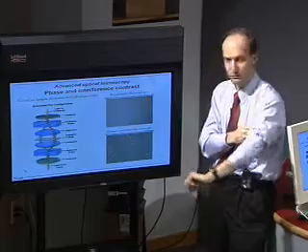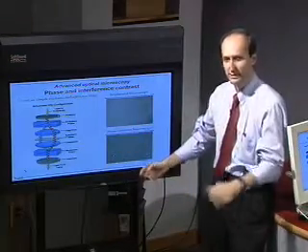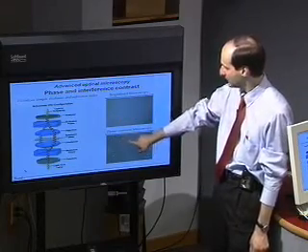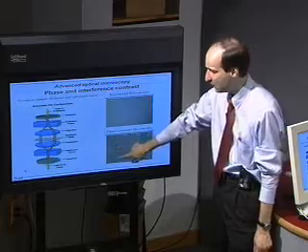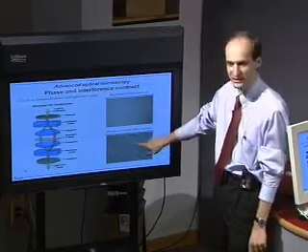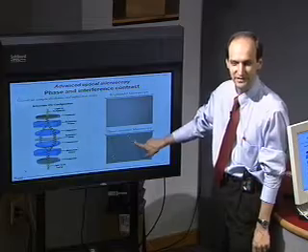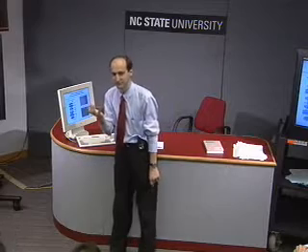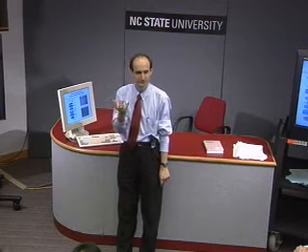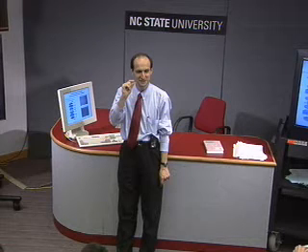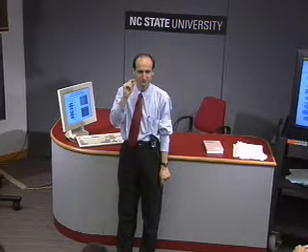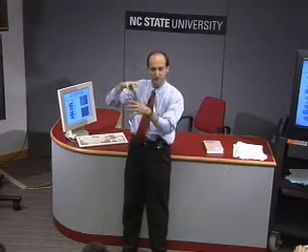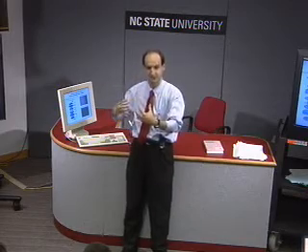This is realized in the microscope in a way about which you don't even care, but it allows you to immediately, instead of seeing this uniformly bright field, if you do phase contrast microscopy, you immediately see any objects which have different optical thickness, like biological cells here. It's a very fast way to immediately get contrast in a sample which is transparent, just because you have the equivalent of thin films in the sample. Again, you just have to pick the right objective and the right illuminator and so on, and they have this phase contrast feature built in.